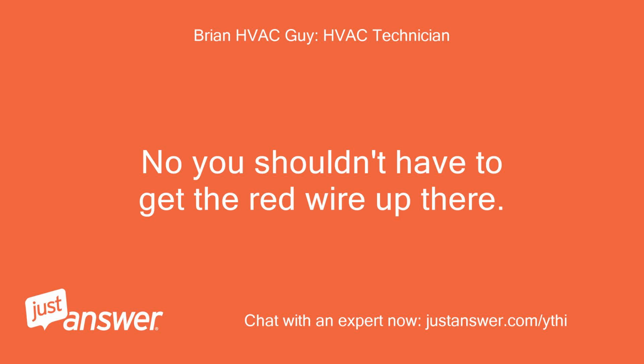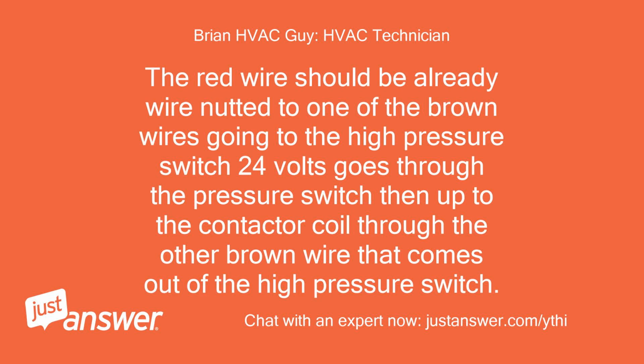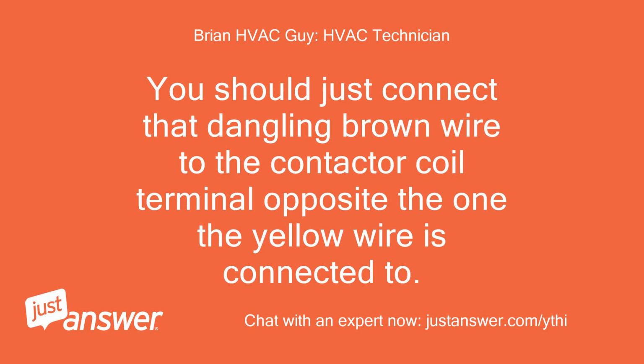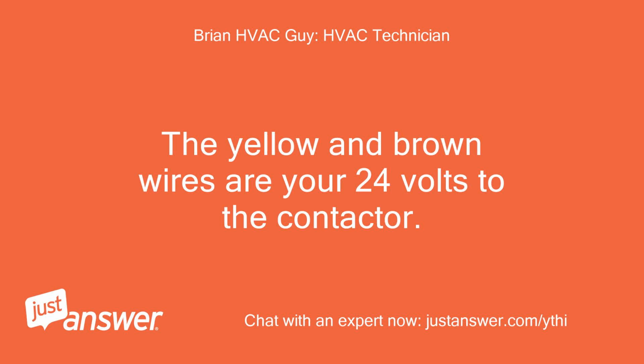No, you shouldn't have to get the red wire up there. The red wire should be already wire nutted to one of the brown wires going to the high pressure switch. 24 volts goes through the pressure switch, then up to the contactor coil through the other brown wire that comes out of the high pressure switch. You should just connect that dangling brown wire to the contactor coil terminal opposite the one the yellow wire is connected to. The yellow and brown wires are your 24 volts to the contactor.